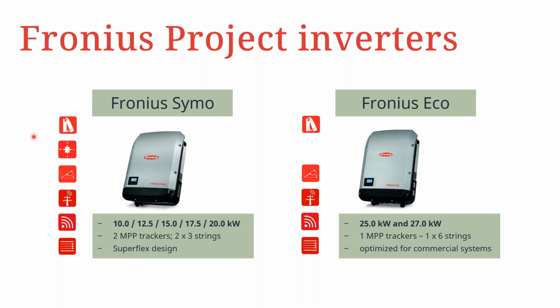So if you are looking at the differentiation between the Fronius Eco and the Fronius Symo, then the biggest differentiator would be the number of MPPTs, because as you can see, with the Fronius Eco, Snap inverter Eco, you have 1 MPPT to which you can connect also maximum 6 strings. But the Superflex design capability is a bit limited for the Fronius Eco. The Superflex basically means that if you have an installation with 2 orientations as far as the PV array is concerned, the Fronius Symo would be able to, let's say, adapt better to these different orientations than the Fronius Eco.